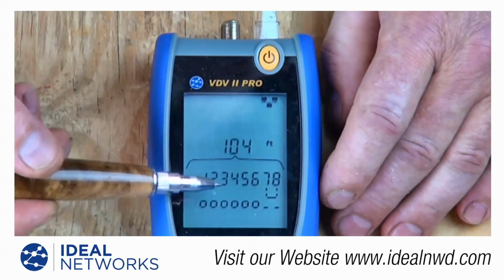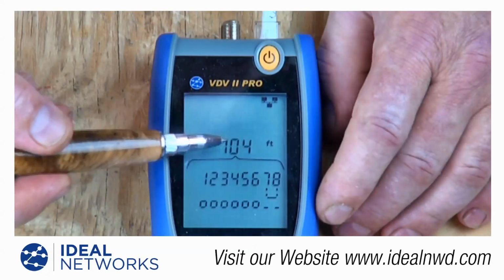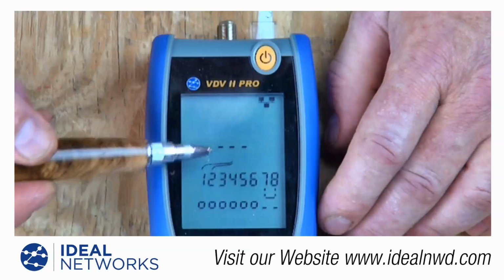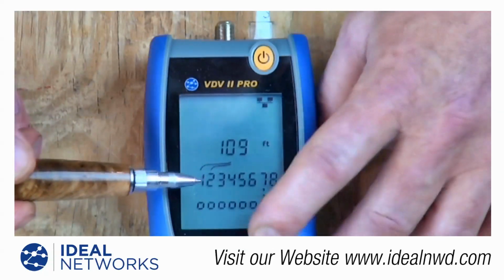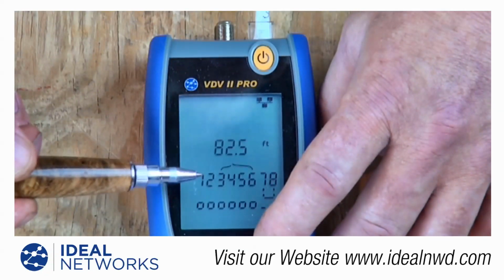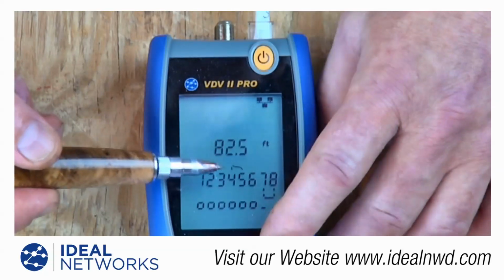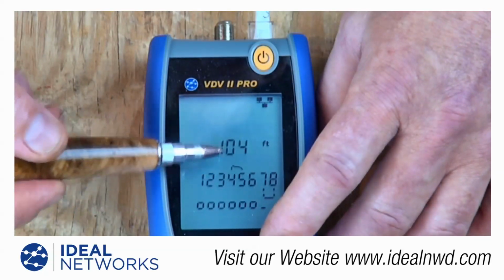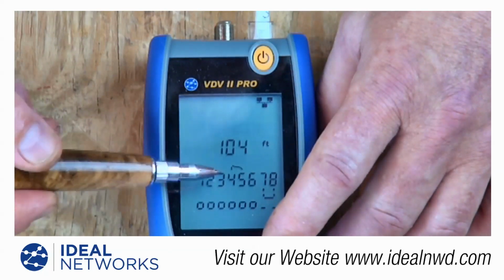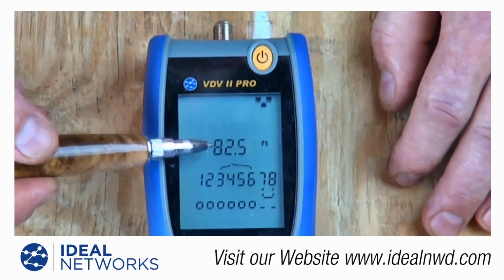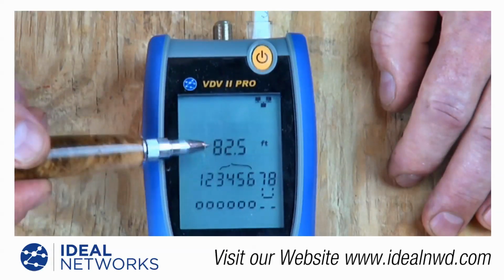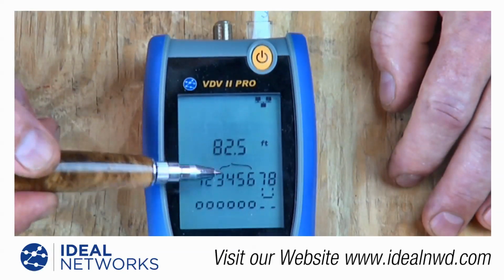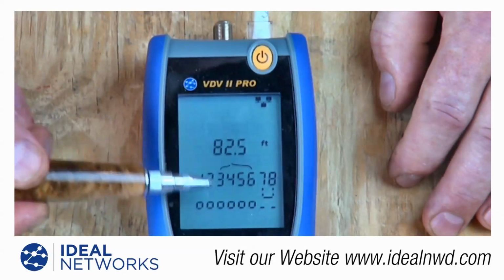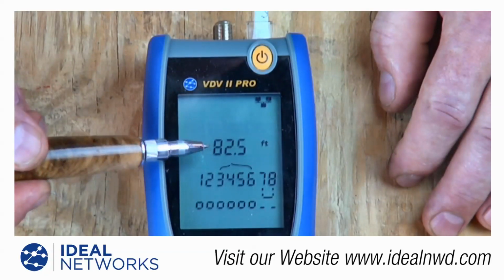And I know 1 and 2 and 4 and 5 were somewhere close. 1 and 2 was pretty close to the 104 foot. We thought it was 109. 3 and 6 is at 82.5, and again 4 and 5 is at 104. So 4 and 5 and 1 and 2 are pretty long, but I noticed that 3 and 6 is a little short. And the reason 3 and 6 is a little short is because there should not be that big of a difference between the longest and the shortest pair, especially in a cable that's only about 100 foot length.